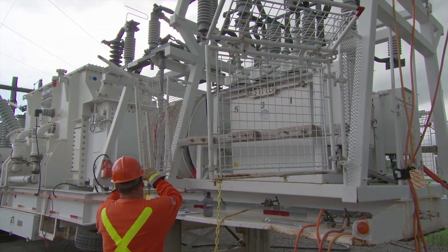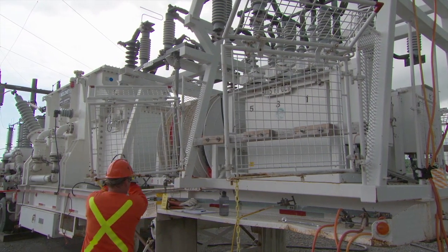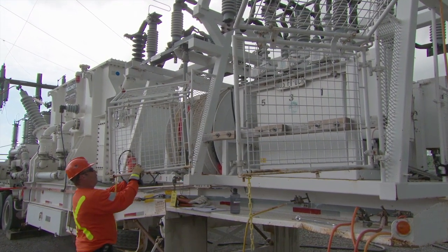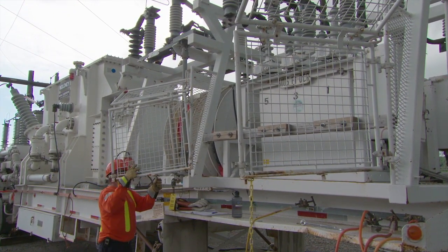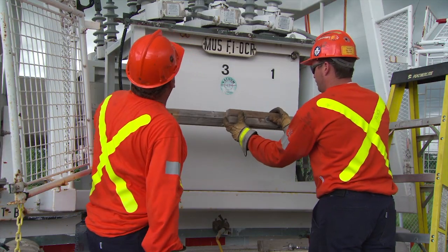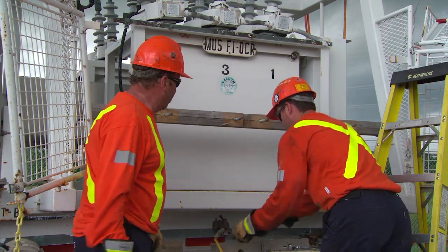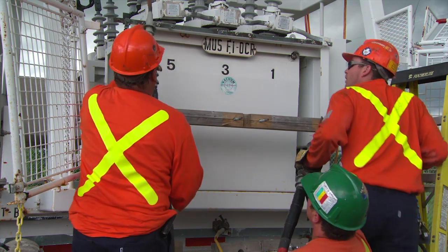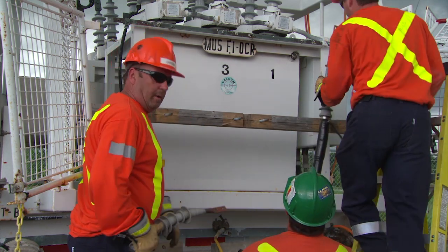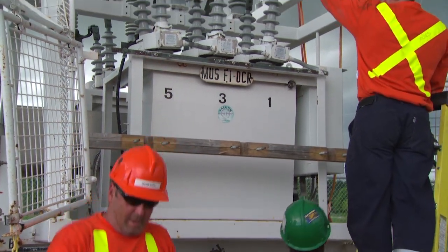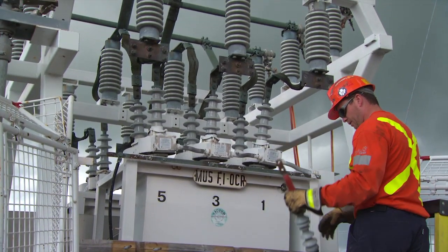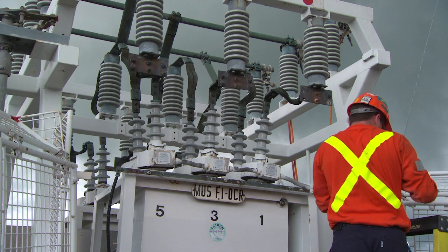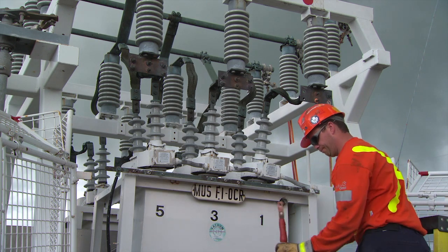Open and secure the MUS recloser gates. Remove the cable support blocks. Connect the neutral cable to the MUS neutral connection bar. Connect the MUS low-voltage cables to the corresponding MUS F1 recloser connection pad, making sure the phasing and feeder numbers match.